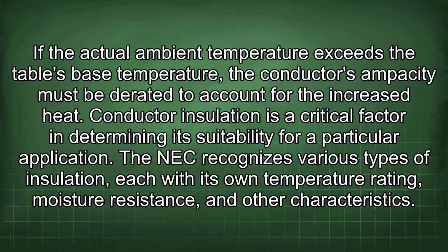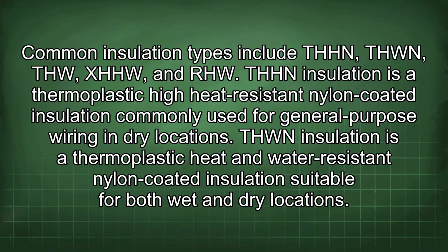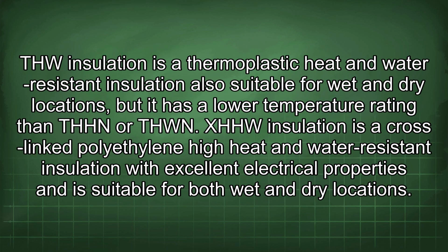The NEC recognizes various types of insulation, each with its own temperature rating, moisture resistance, and other characteristics. Common insulation types include THHN, THWN, THW, XHHW, and RHW. THHN insulation is a thermoplastic high heat resistant nylon coated insulation commonly used for general purpose wiring in dry locations. THWN insulation is a thermoplastic heat and water resistant nylon coated insulation suitable for both wet and dry locations. THW insulation is a thermoplastic heat and water resistant insulation also suitable for wet and dry locations, but it has a lower temperature rating than THHN or THWN. XHHW insulation is a cross-linked polyethylene high heat and water resistant insulation with excellent electrical properties and is suitable for both wet and dry locations.